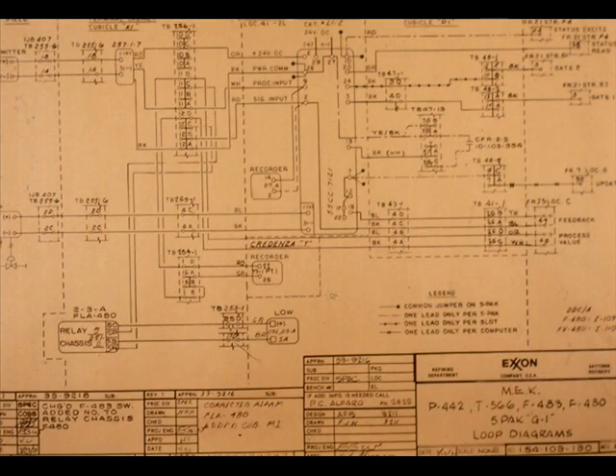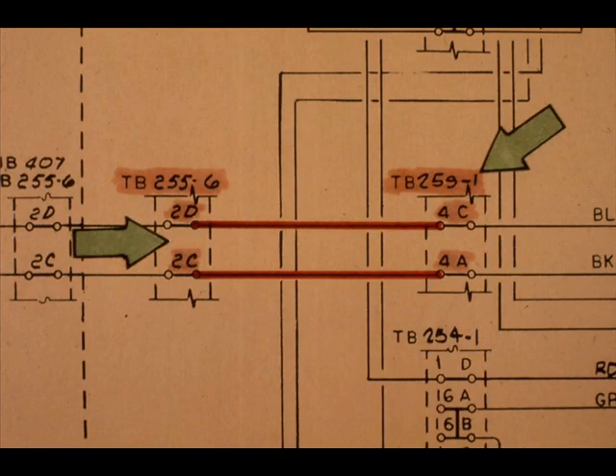Once again, the loop diagram shows us the signal path only. Other documentation shows us precisely how a particular cable pair, or pairs, is used to carry a signal. For instance, look at the controller output circuitry. The path is from TB255-6, terminals 2C and 2D, through TB259-1 to the controller output module.